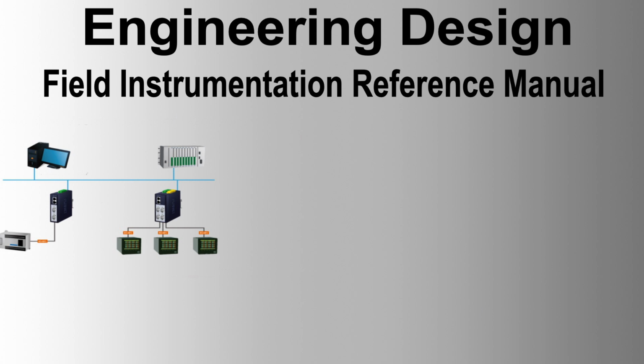Accessibility levels. Accessibility levels for instruments are defined to ensure safe and easy access for operational attention and maintenance. Instruments should be installed considering their location and accessibility, avoiding excessive vibration and ensuring proper representative measurements. Protective shades may be used in tropical and subtropical areas to protect instruments from sun radiation and rain.